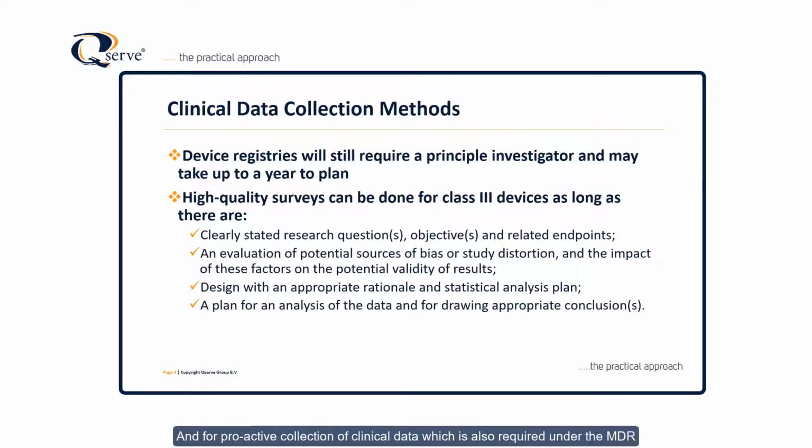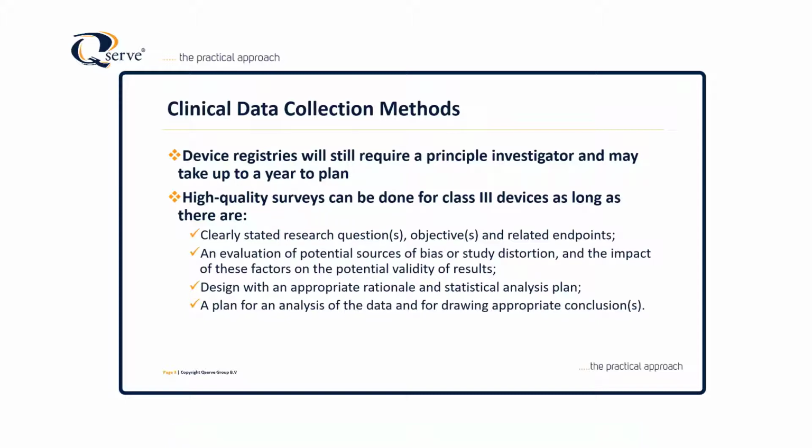And for proactive collection of clinical data, which is also required under the MDR, instead of clinical investigations, you can look at device registries and high-quality surveys, depending on the type of data that you need to collect. Keep in mind the amount of time that's required. Device registry searches may be faster than clinical investigations, but they still require a principal investigator, and they may take up to a year to plan.